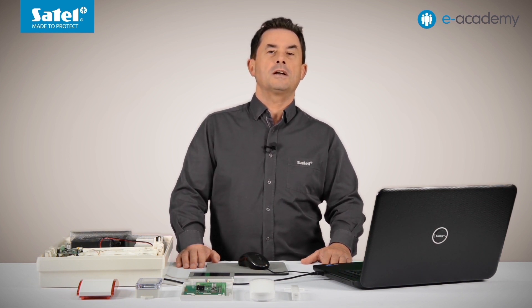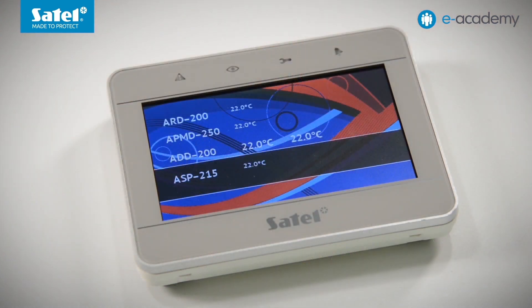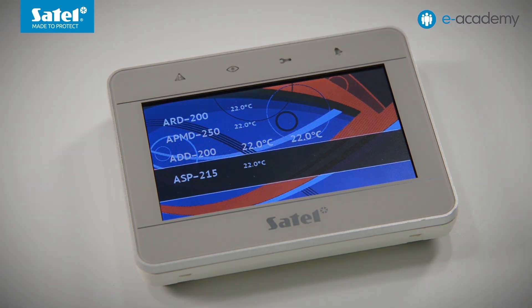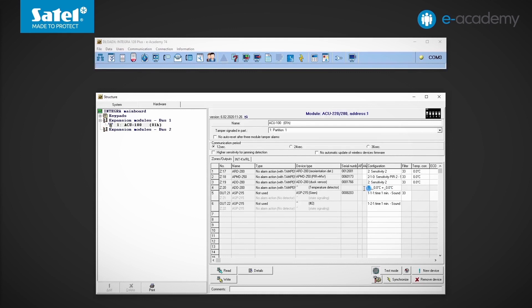So let's check how it works in practice. On the keypad, we check what the temperature measured by the ADD-200 detector is. This detector is located inside a room where it is quite warm. So we set the low threshold, a temperature of 15 degrees Celsius and a tolerance of 2 degrees. We write the data to the controller.